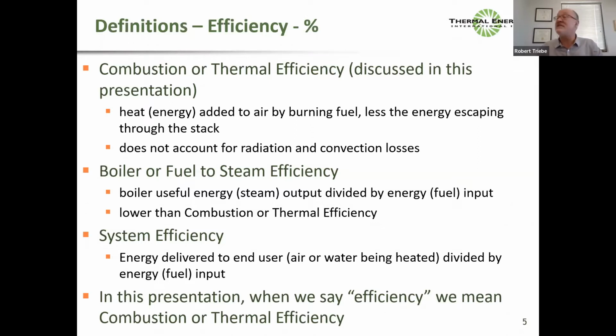Boiler or fuel to steam efficiency. That's the boiler useful energy divided by the energy input. It's obviously lower than the combustion or thermal efficiency because we do have radiation losses. Some places will even include the deaerator steam load as a steam loss in this boiler to steam efficiency, because the deaerator can have a significant steam load. Do you consider that useful steam or not? That determines how you define your boiler steam efficiency. So every plant even defines that number differently.